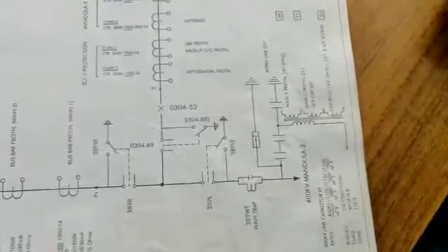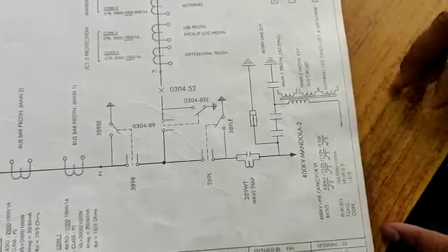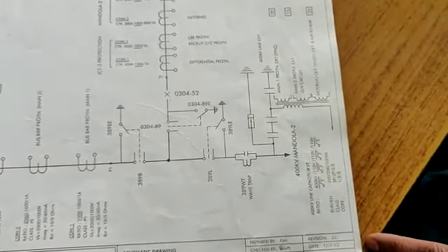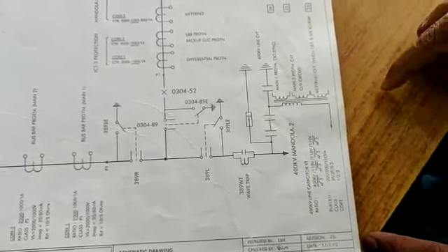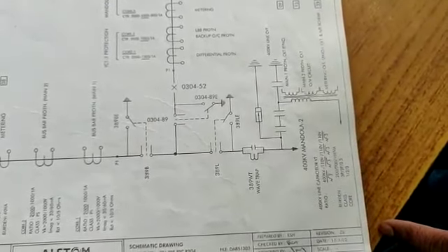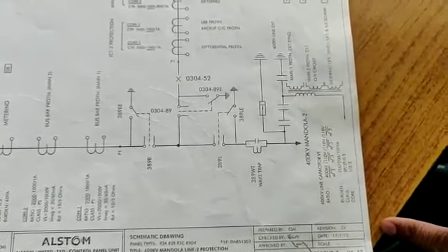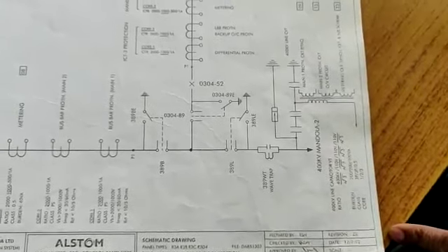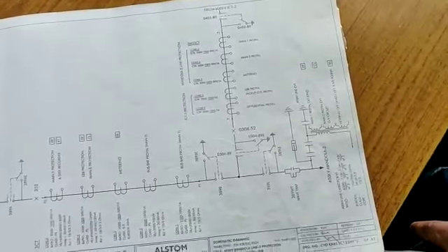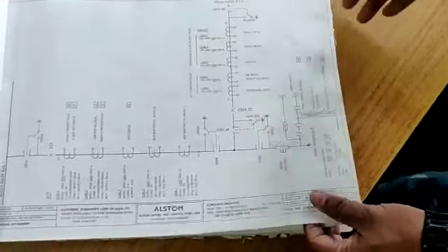In this CVT, or in any CVT used in the power grid, there are only 3 cores, and these 3 cores are designated as core 1, core 2, core 3, and in all those cores your CVT ratio will always remain the same, that is 400/110, because the secondary voltage will always be 110. Out of those 3 cores, core 1 and core 2 will always be used for main 1 and main 2 protection of transmission line, and core 3 is used for metering or check sync or synchronization circuits.